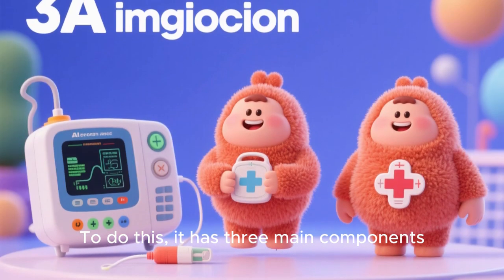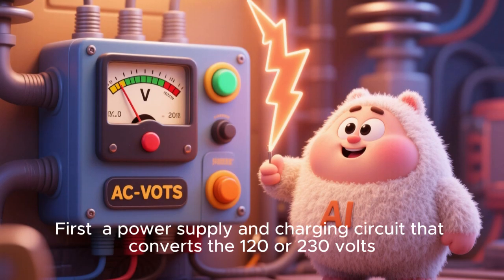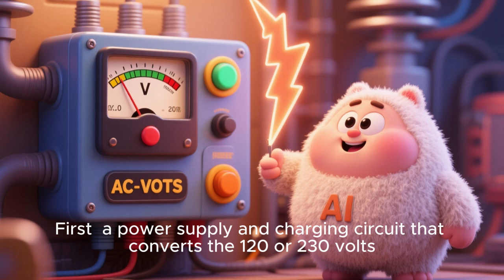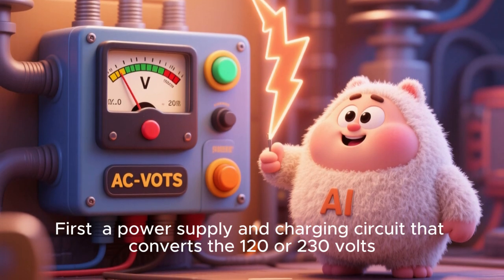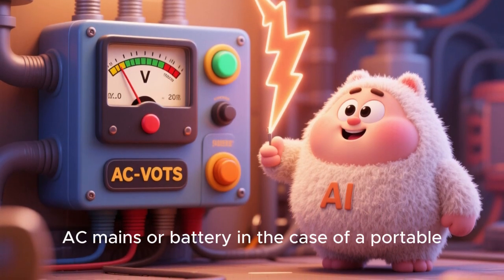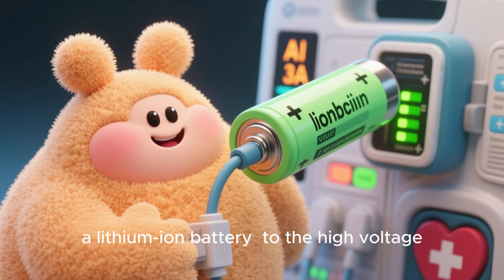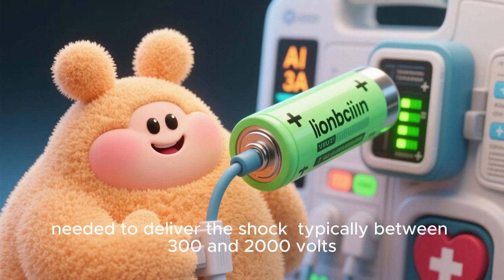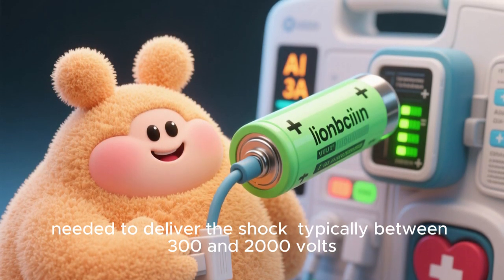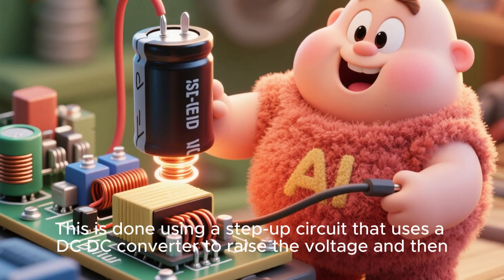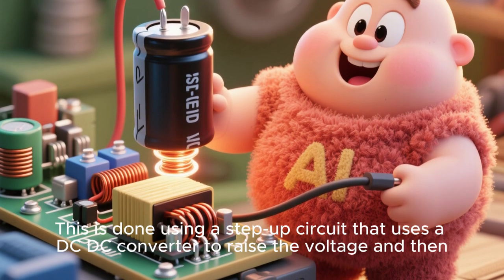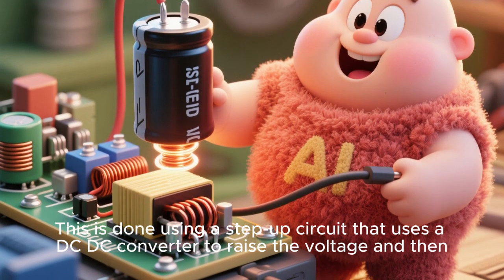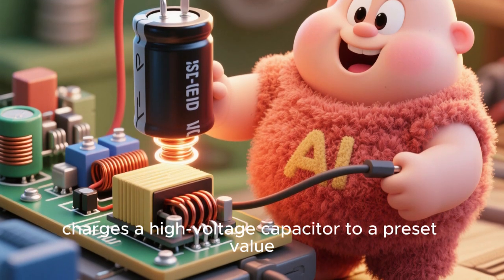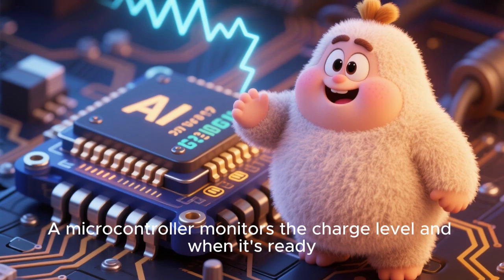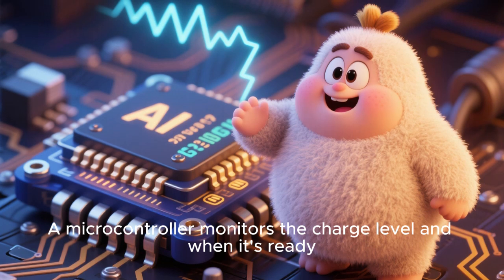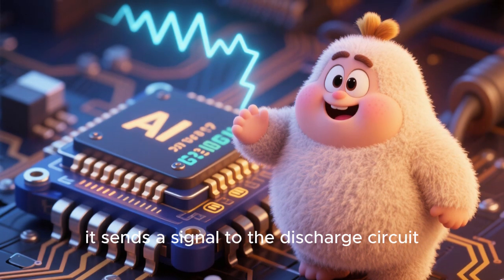To do this, it has three main components. First, a power supply and charging circuit that converts the 120 or 230 volts AC mains, or battery in the case of a portable AED, a lithium-ion battery, to the high voltage needed to deliver the shock, typically between 300 and 2000 volts. This is done using a step-up circuit that uses a DC-DC converter to raise the voltage and then charges a high-voltage capacitor to a preset value. A microcontroller monitors the charge level, and when it's ready, it sends a signal to the discharge circuit.